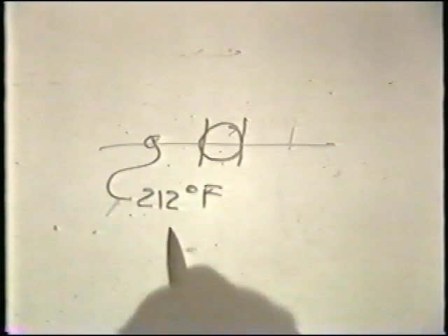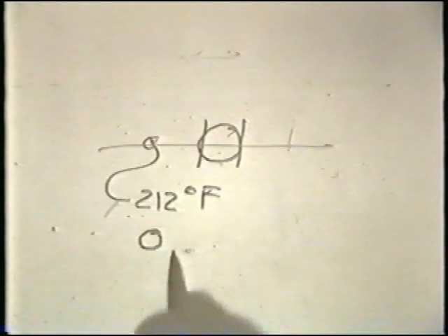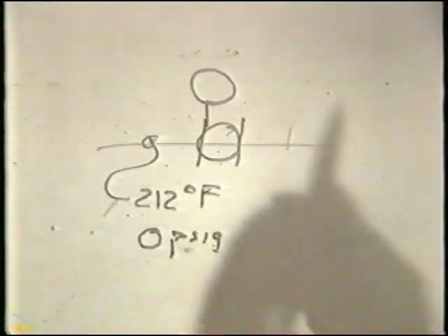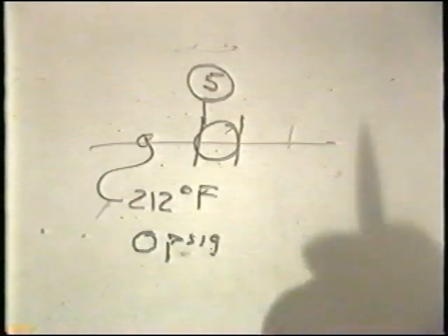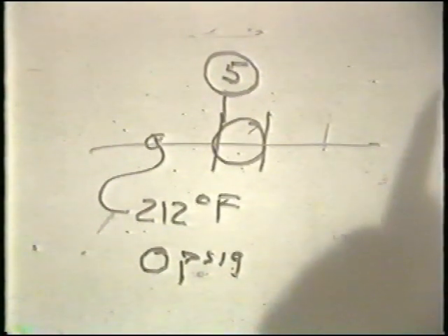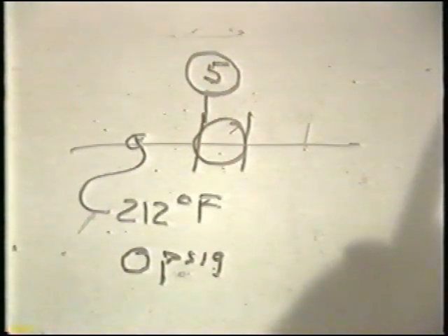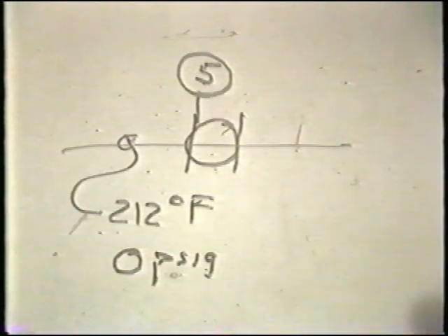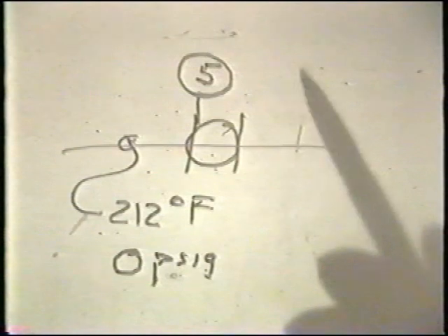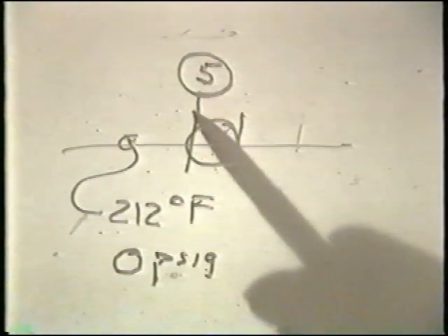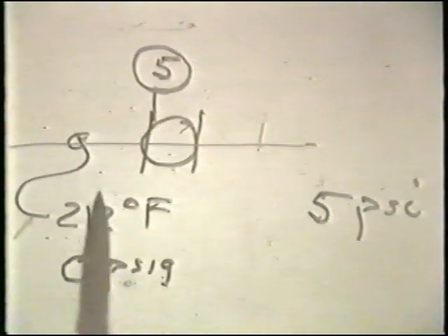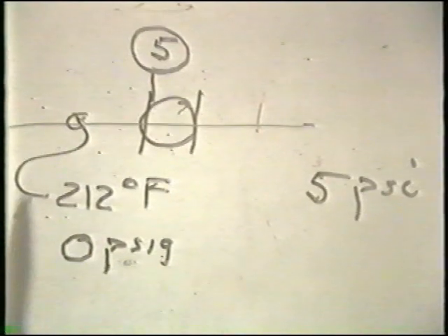And we know that for this condition, our flash point is 0 psig. Now we know after evaluation of this pumping system that a gauge mounted at the pump suction flange would register 5 psig. This is by evaluation of the piping plans. So we would then have an available NPSH, or pressure available at the pump suction flange, of 5 psi over and above the liquid flash point.